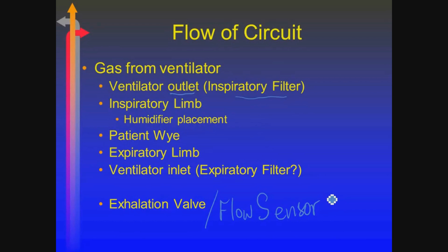In addition to having a valve there, you need to have a flow sensor. The flow sensor is monitoring the volume that is being passed by, so I know what my tidal volume on the exhaled side is. This exhalation valve, by the way, is also how PEEP is created, because it keeps a small amount of pressure in there.